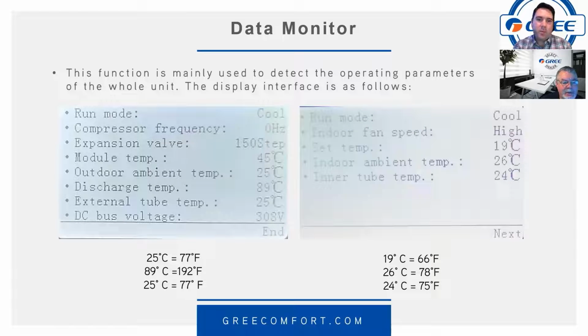And showing the readings in Celsius. I converted them down here, but this function detects the operating parameters for the whole unit. And this is the mini split, the single zone one that you were looking at, not the multi-zone. So if you're hooked to the outdoor unit, you're able to see the outdoor ambient temp that it thinks it is. You can compare that to see if it's correct. You can see what your discharge temp thinks that it is. Compare that, take an accurate reading off of the discharge pipe and see if it's fairly accurate within plus or minus 10%.